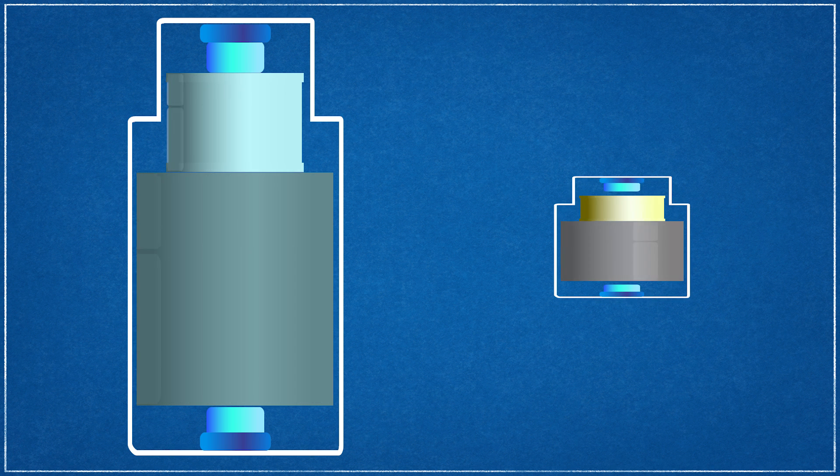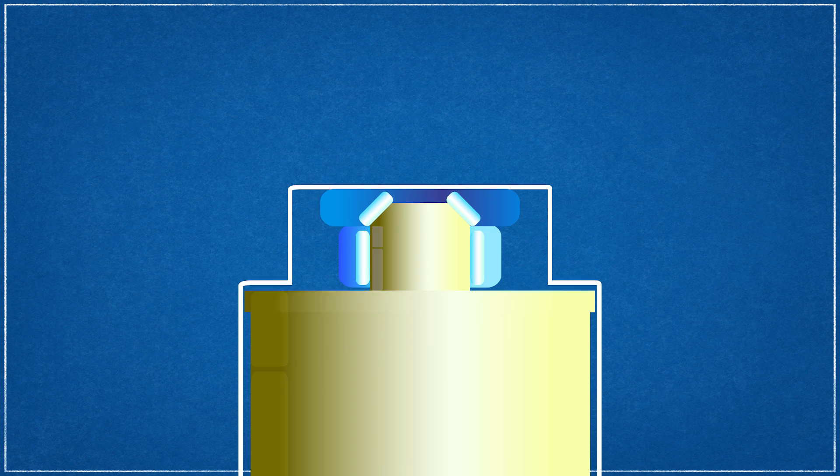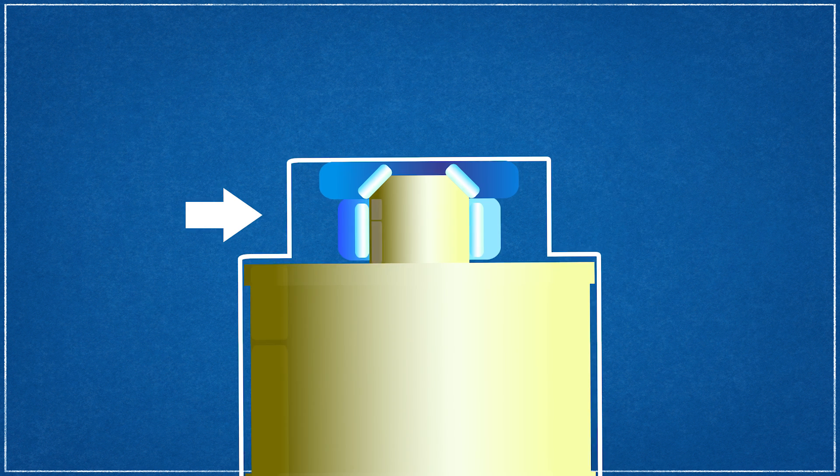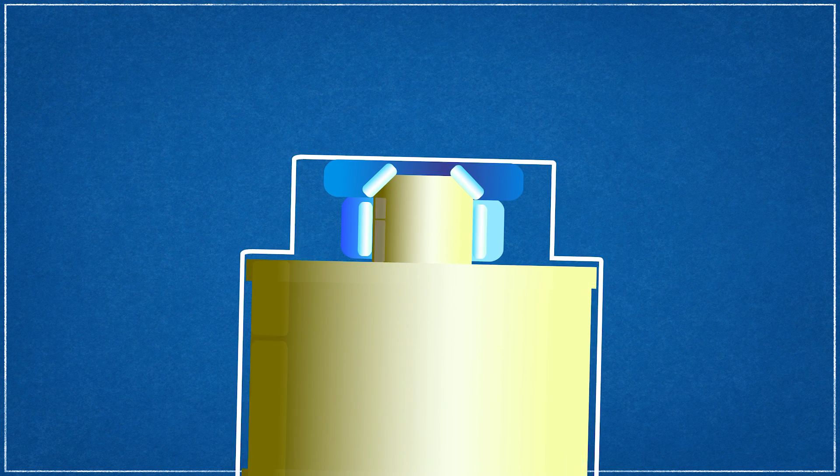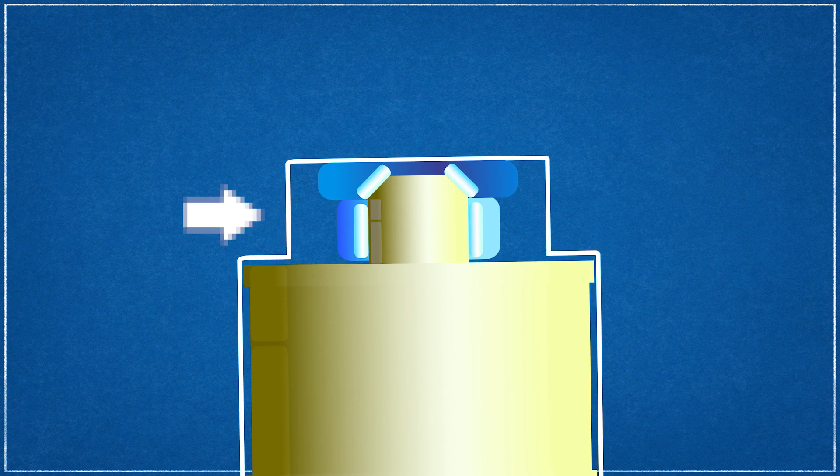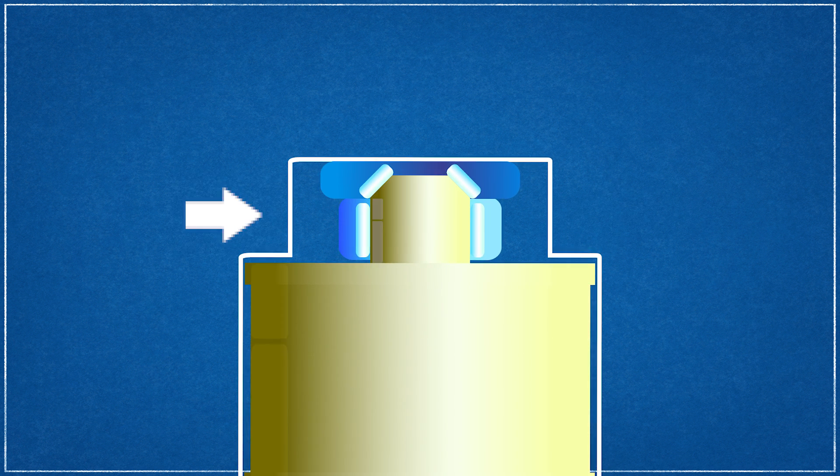Because flywheel energy storage systems usually enclose the flywheel within a vacuum to reduce friction, the primary point of energy loss happens at the bearings that support the flywheel. Not only must the bearings support the flywheel, but also resist the forces resulting from its changing orientation, especially the persistent rotation of the earth. These changes are resisted by the gyroscopic forces exerted by the flywheel's angular momentum, which exerts a force against the bearing system.